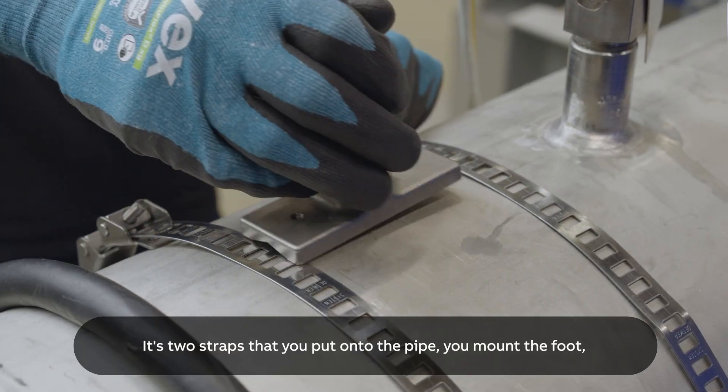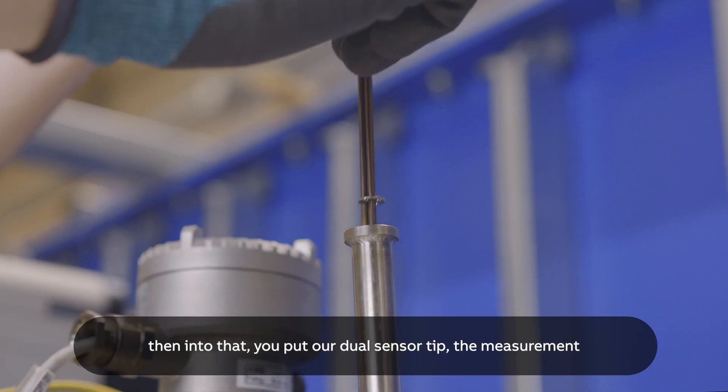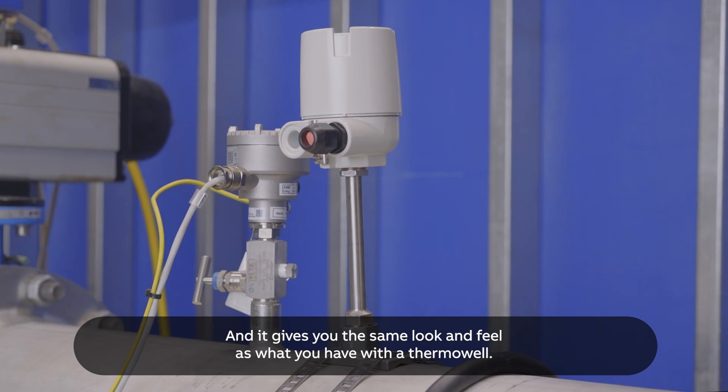It's two straps that you put onto the pipe, you mount the foot, then into that you put our dual sensor tip, the measurement insert inside, screw the head together, and off you go. It gives you the same look and feel as what you have with the thermowell.